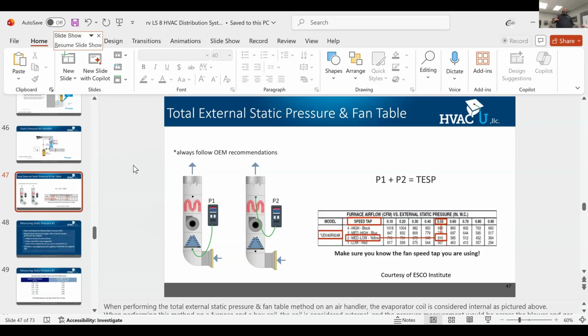Once you start getting into the 0.9s and 1 inch of water column, above 0.8, that's when you start to have equipment problems with the new modulating equipment. So that's one key clarification. When you look at air handlers, many of them are rated at 0.8. The coils are integral, so the duct modifications that you do are going to impact that total external static pressure. So we don't necessarily strive for 0.5. That's the test pressure for a gas furnace.